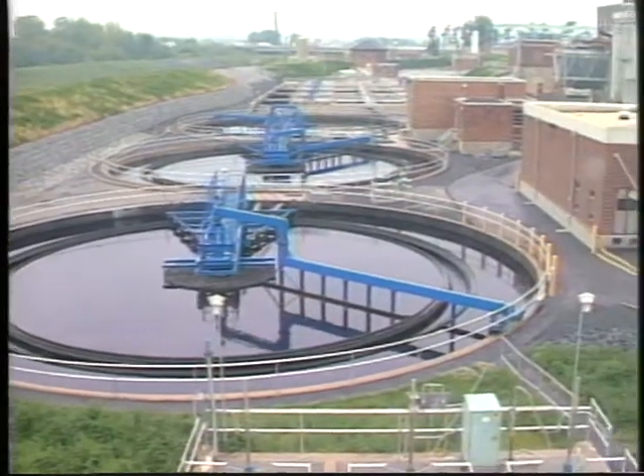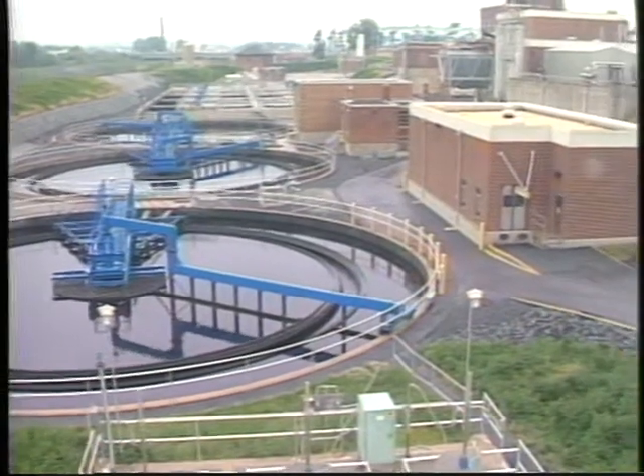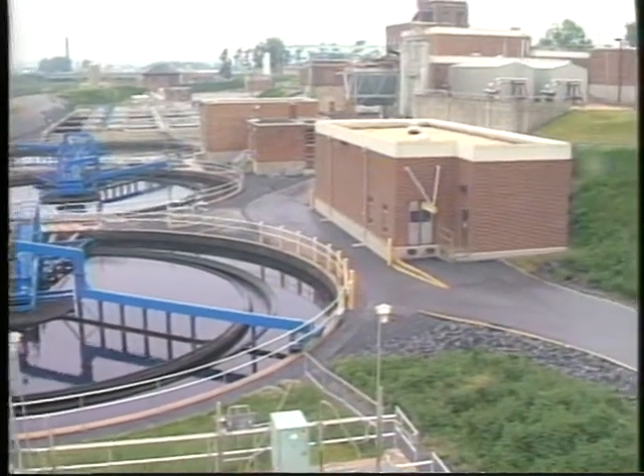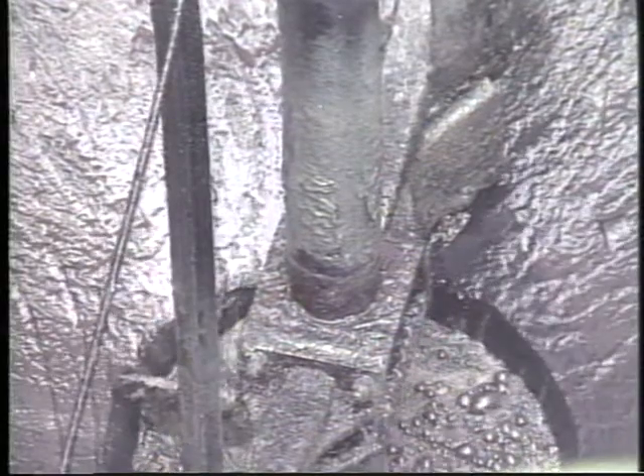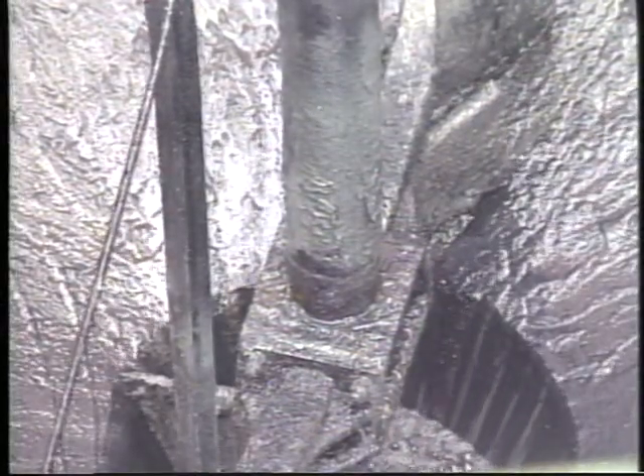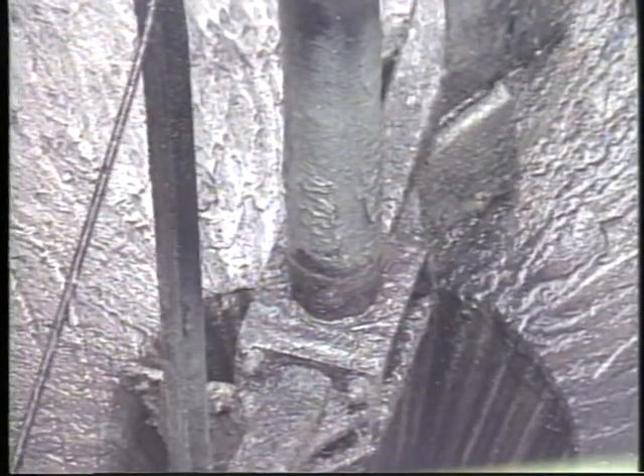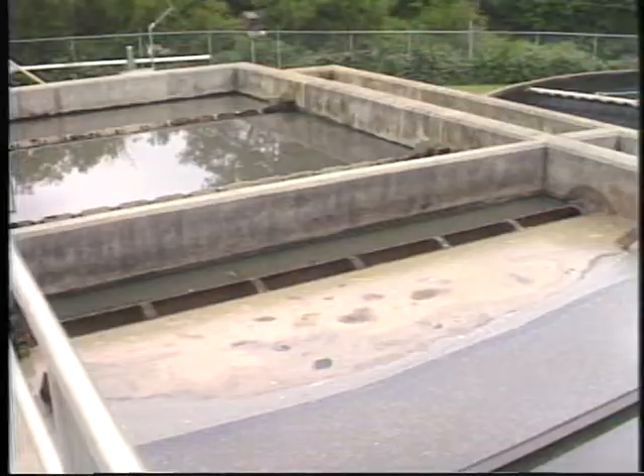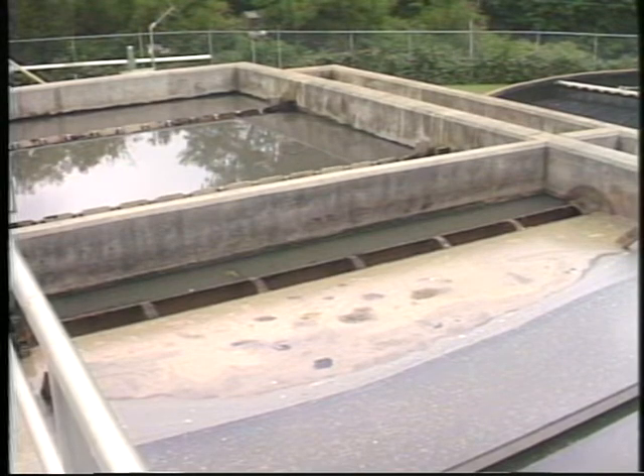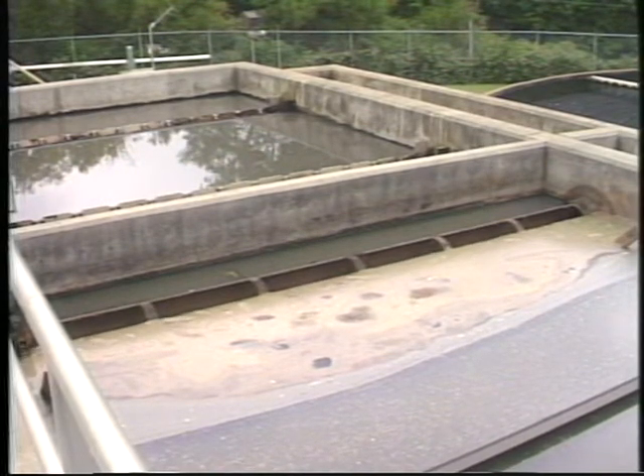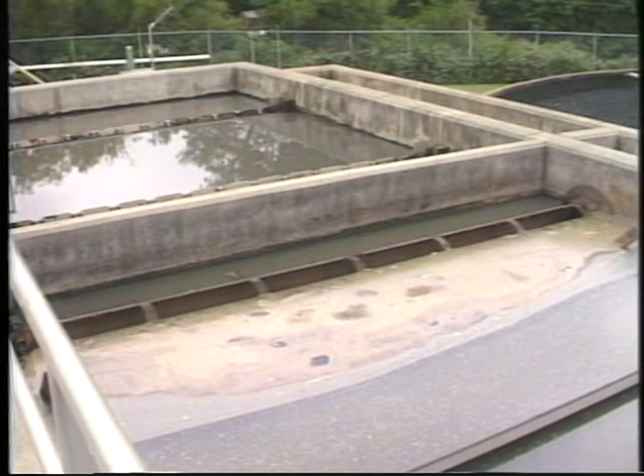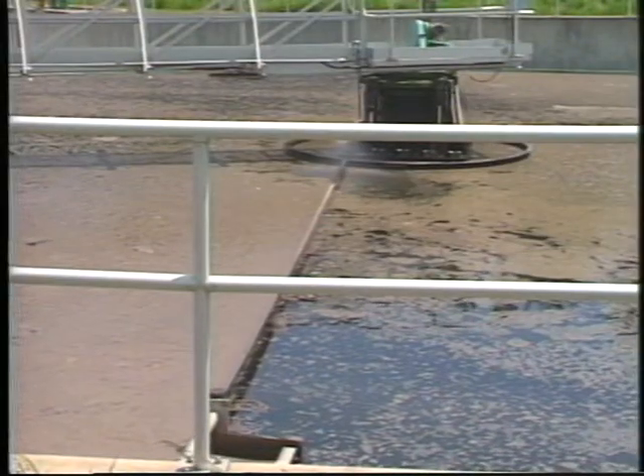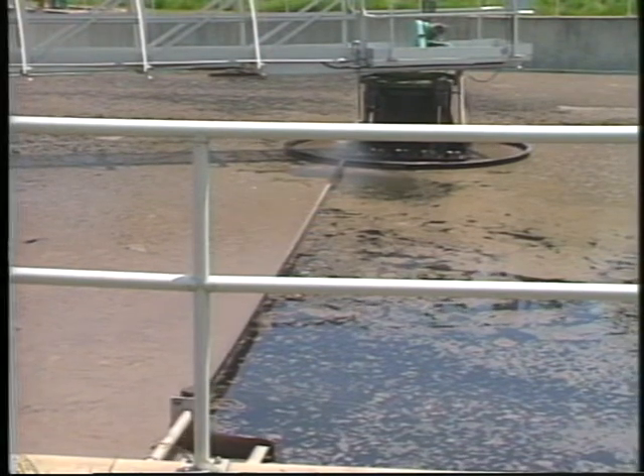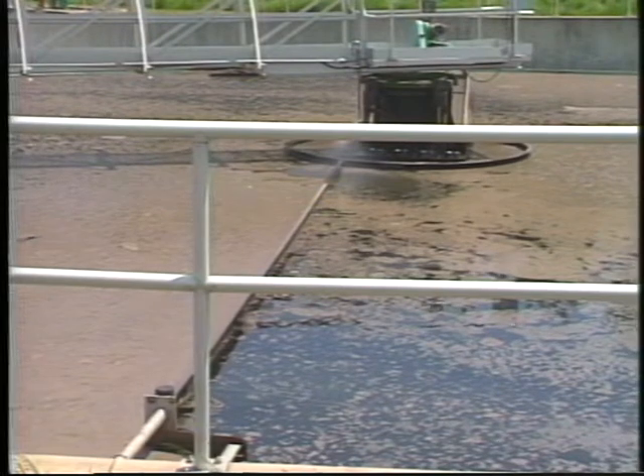In any event, the solids removed from a secondary clarifier are different from the solids removed in primary clarifiers. The settleable solids removed from a primary clarifier tend to be much denser than those removed from a secondary clarifier. Biosolids from primary clarifiers may also exhibit anaerobic or septic conditions as opposed to aerobic secondary biosolids. The floatable solids in a primary clarifier consist of grease, oil, hygiene products, and other materials that will float. Floatable solids found in a secondary clarifier are usually oxidized organic matter from the preceding biological treatment stage.